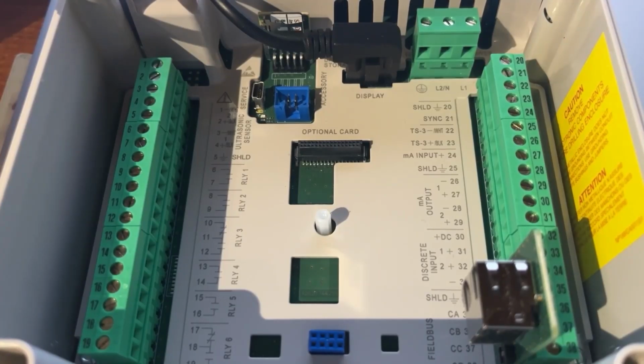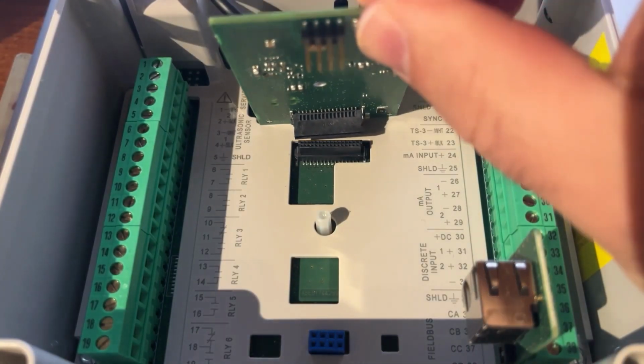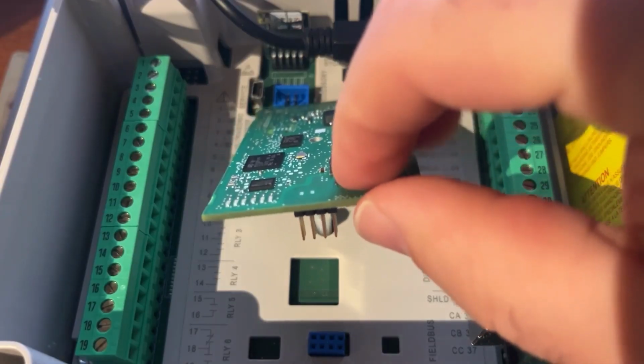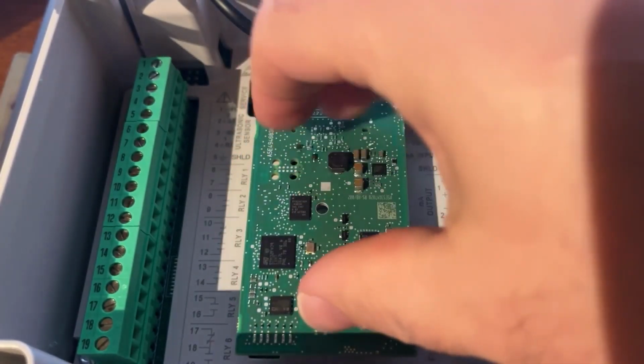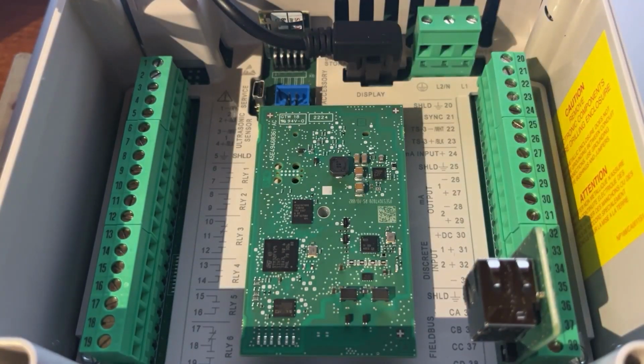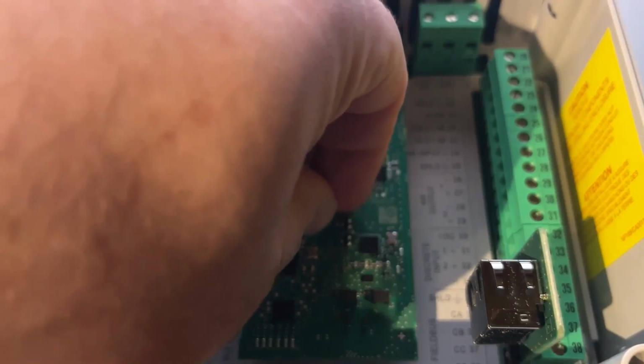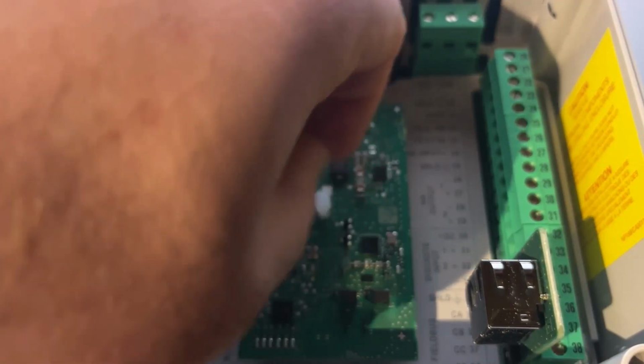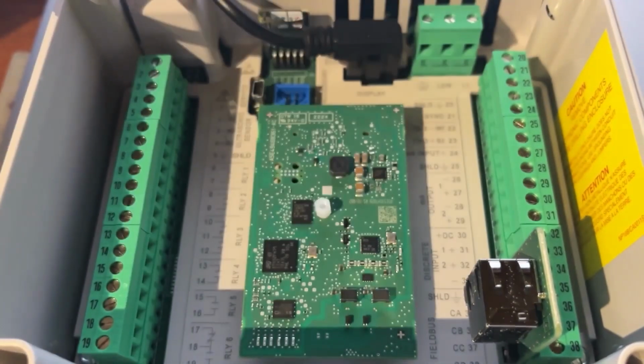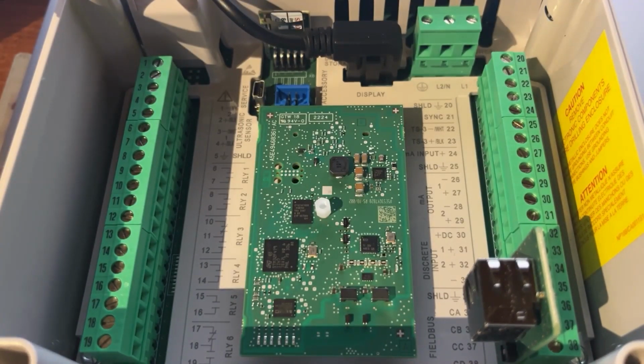So to install a card in the field, I find the easiest thing to do is there's 2 pin rows, is to line up these black connectors like this, and then just slide down the others to make sure you have a nice positive contact. And then there's a small little plastic screw that goes in to the standoff in the middle, and we'll just install that as well to make sure that the comms card is secure during use. So that's it. Very quick and easy. Those cards are swappable, so you can remove one, add a different one, add one after the fact.